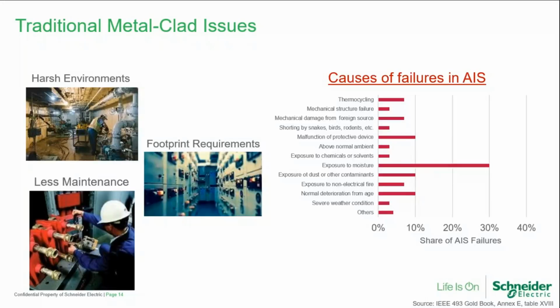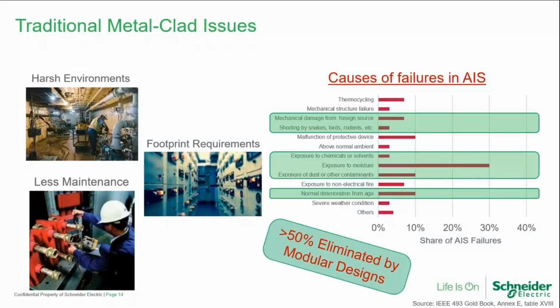If I look at which of these contributors are applicable to AIS but not applicable to GIS and SIS, things like mechanical damage from foreign sources, exposure to all those environmental contaminants, and even the normal deterioration caused from age in AIS, which is reduced in GIS and SIS styles of design, we can eliminate greater than 50% of the main causes of failure with traditional styles of gear by using some of the newer styles of switchgear, things like GIS and SIS. So at the end of the day, that's the whole point. We're trying to develop newer styles of switchgear that are going to last longer, be more reliable, require less maintenance, as well as increase safety and decrease the amount of footprint that's required.